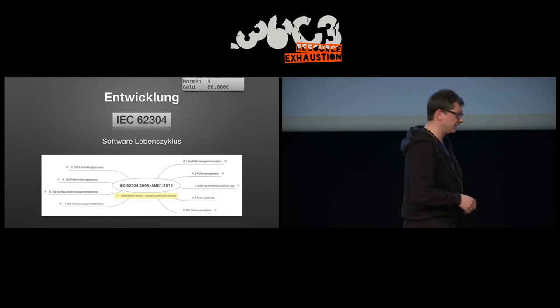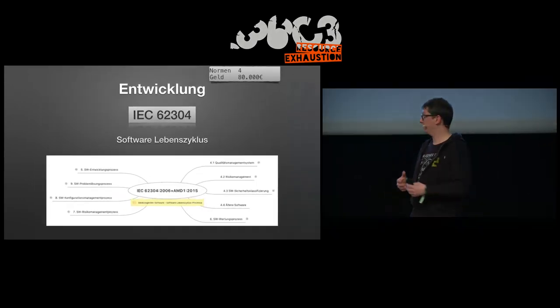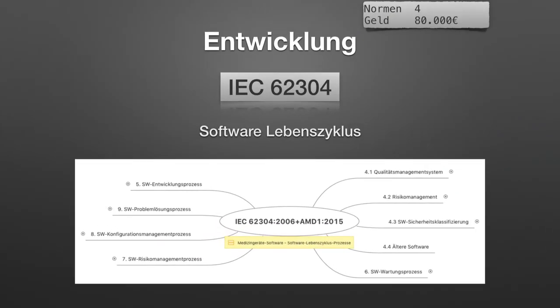And the next standard that we mentioned already is IEC 62304. That's a pure software norm, as a standard. It was developed in a time when people thought that software is always part of a medical software product. But then there were medical products whose software was so bad that their own standard had to be invented.